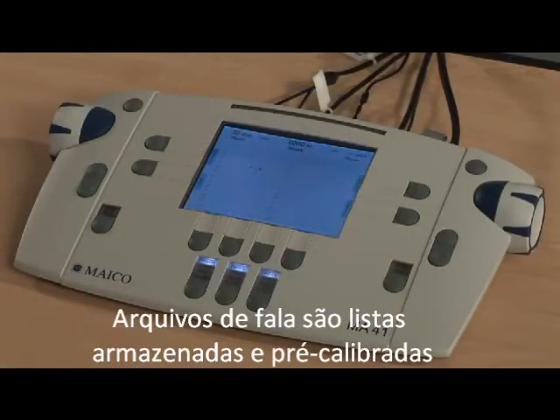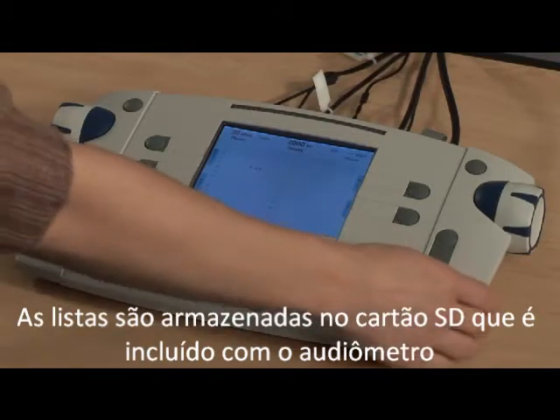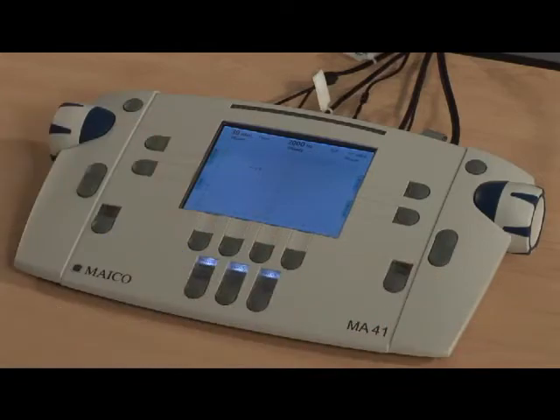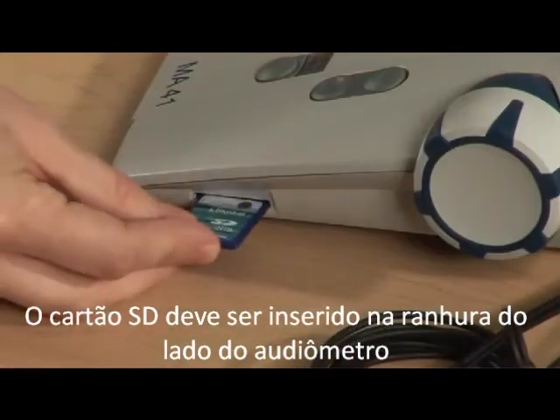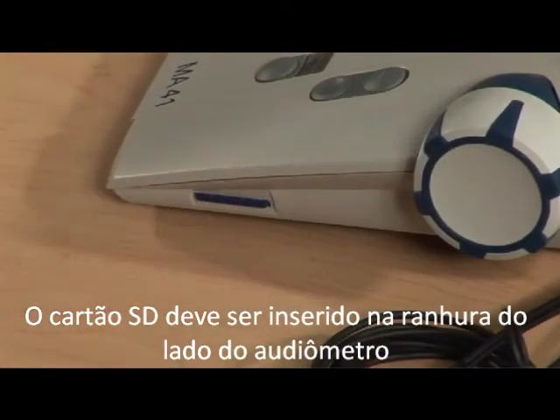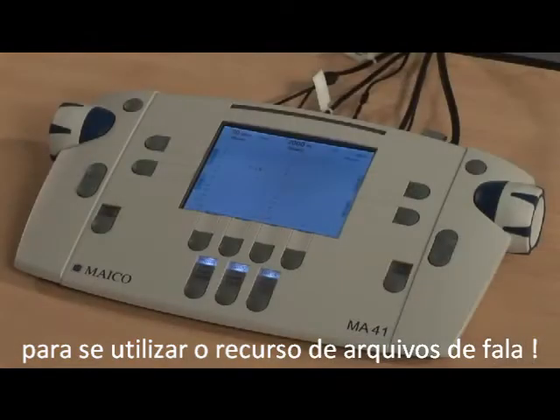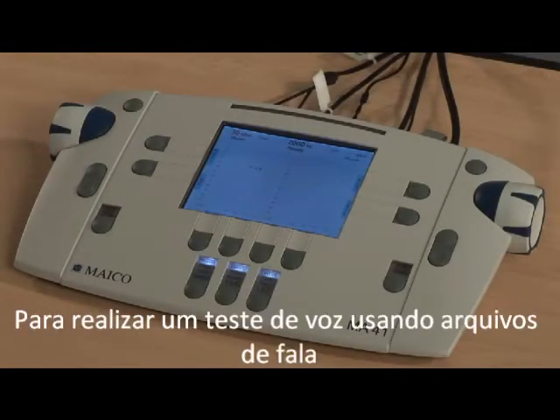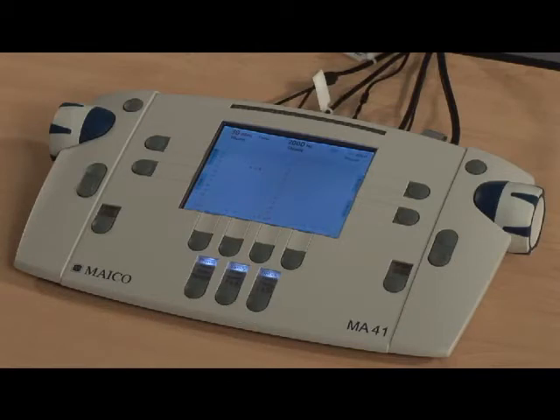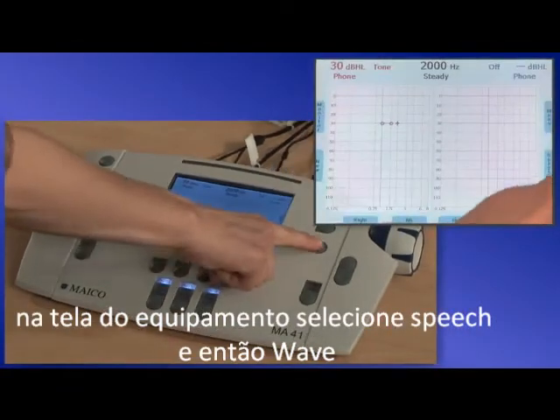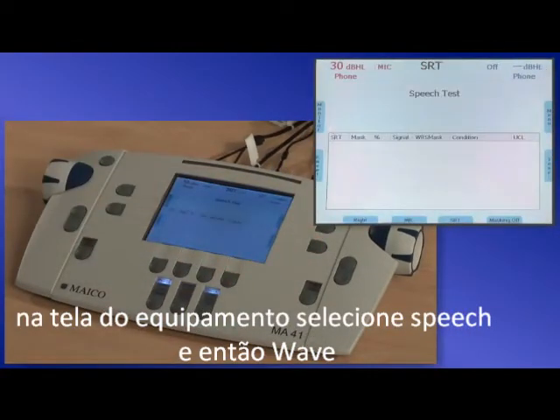WAV files are stored speech lists that are pre-calibrated. The lists are stored on the SD card that is included with the audiometer. The SD card must be inserted in the side slot of the audiometer in order to use the WAV file feature. To conduct a speech test using WAV files, select the speech screen, then select WAV.